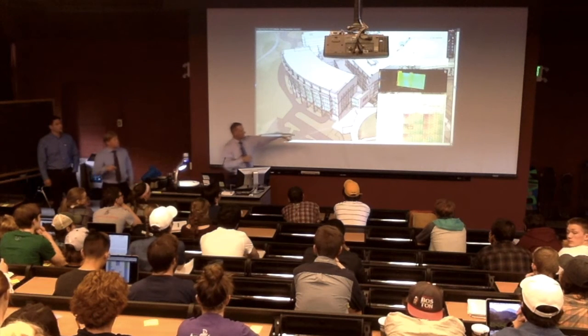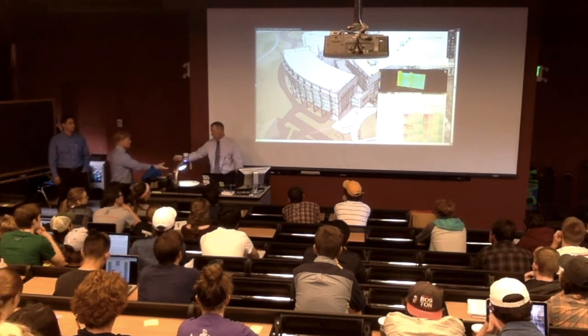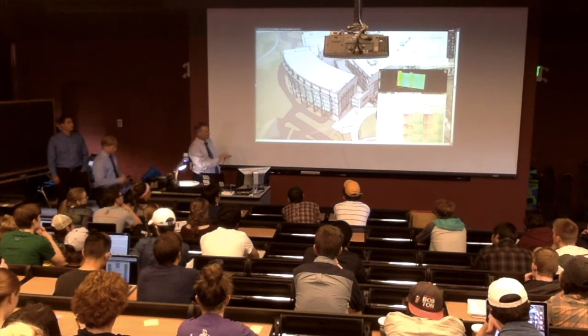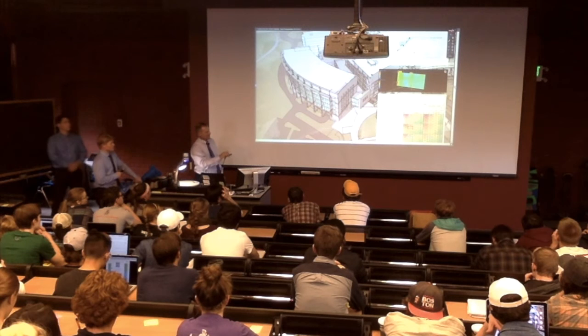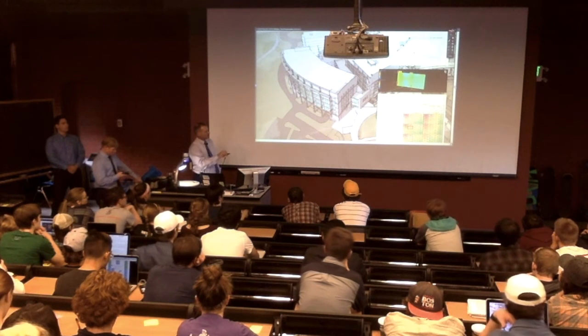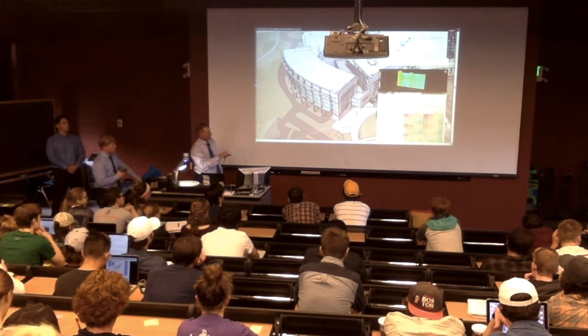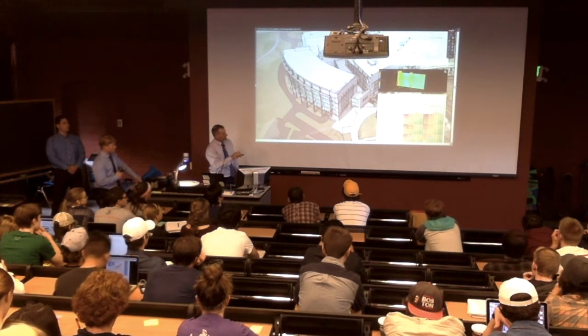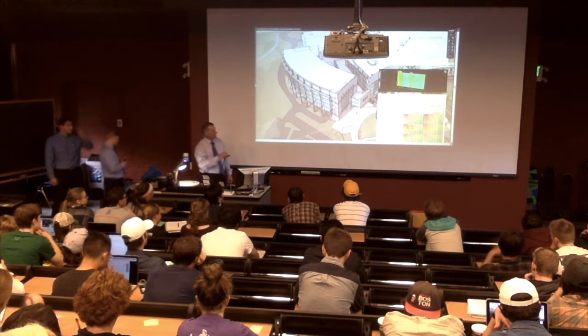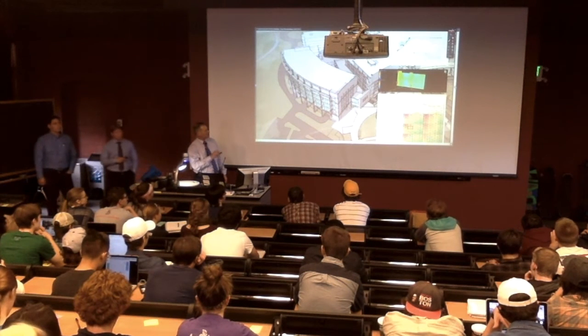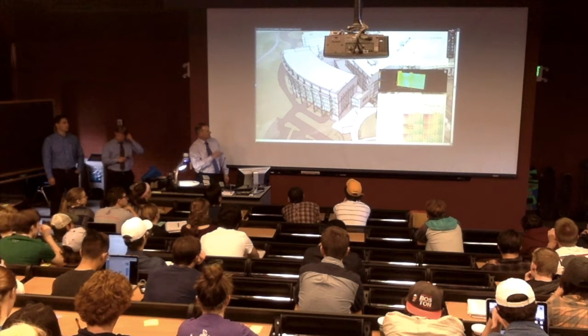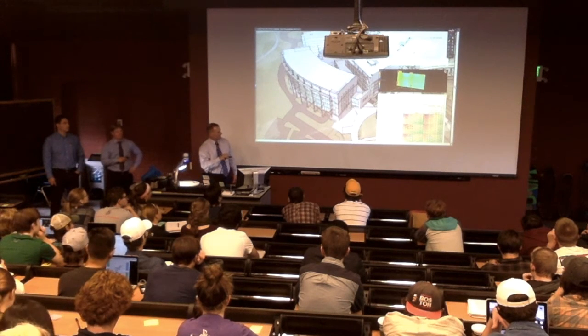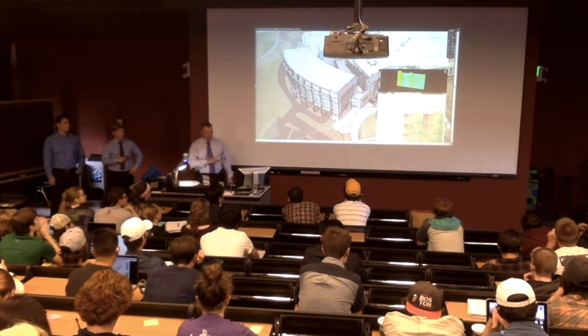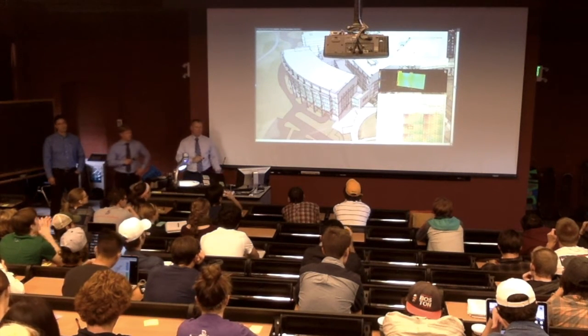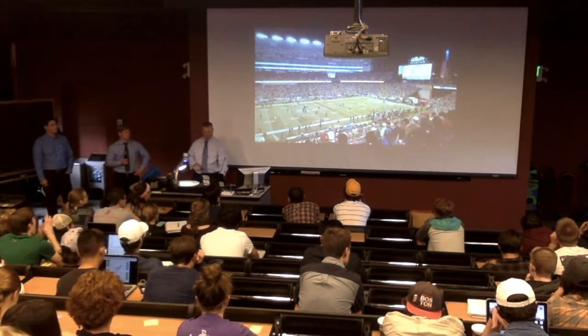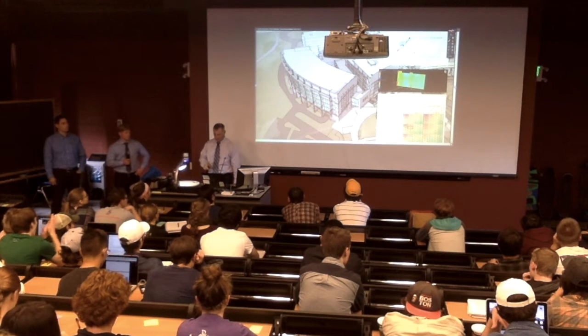But we looked at... So this chart has, you can see it, maybe people in the front row, but this says U value, and it has different U values associated. Solar heat gain coefficient, overhang ratio, and this is the orientation north-south. And what we tried to do is analyze what the best orientation for the building is, how much wall, window, how much shading, like these are solar shading things. So this analyzed and it picked this one particular thing as the best design for that building. Now, I'm not sure if exactly they used that, but at least it was a tool that they utilized to understand how they could make this building better.